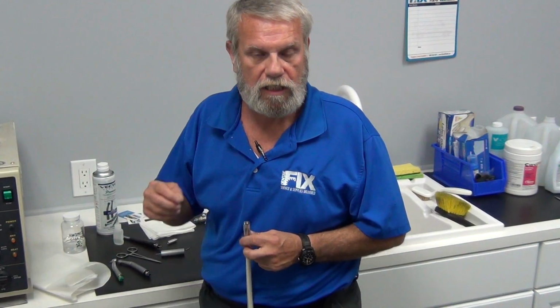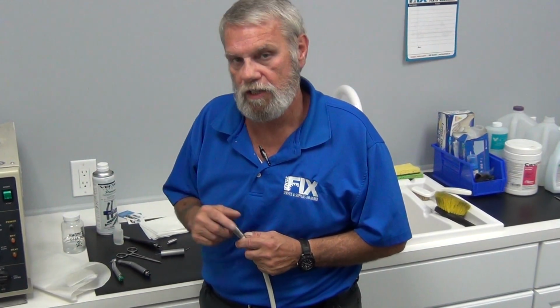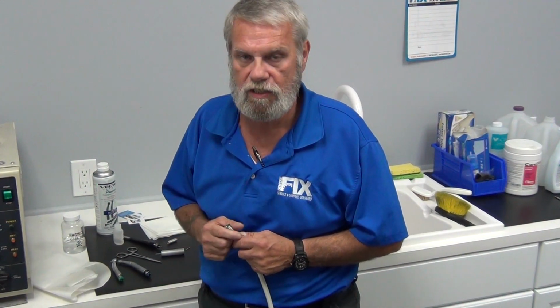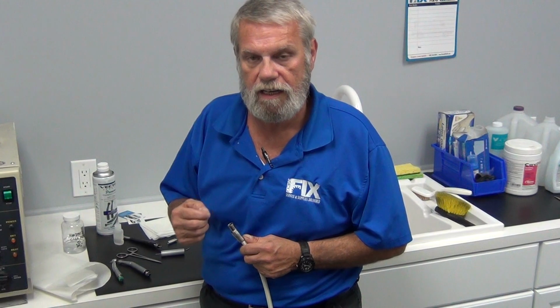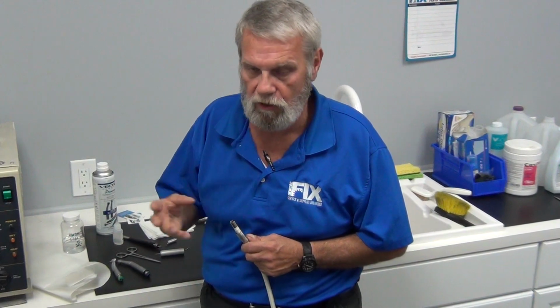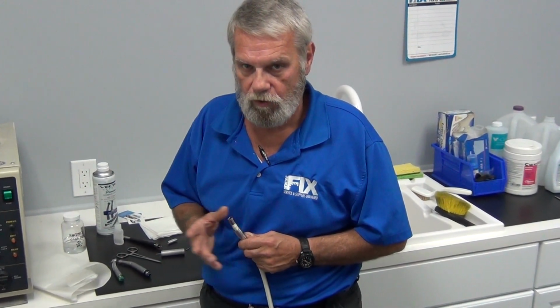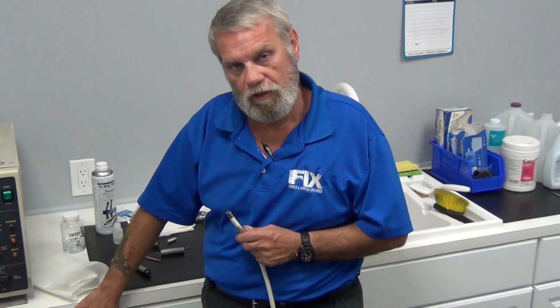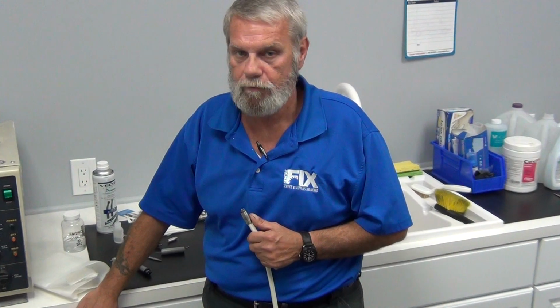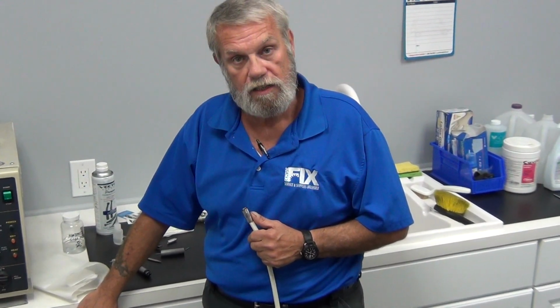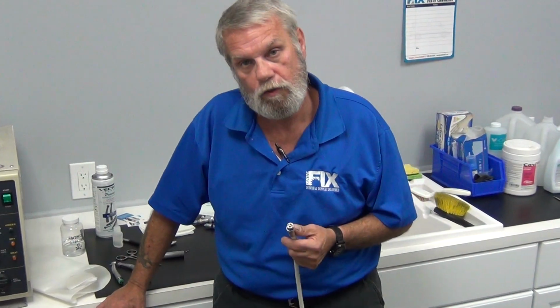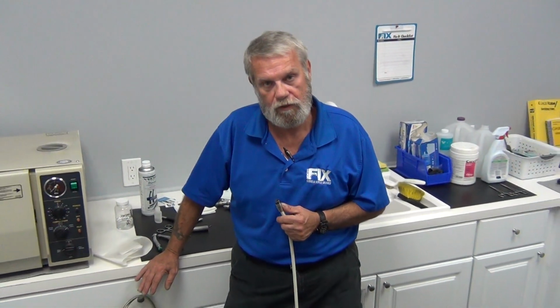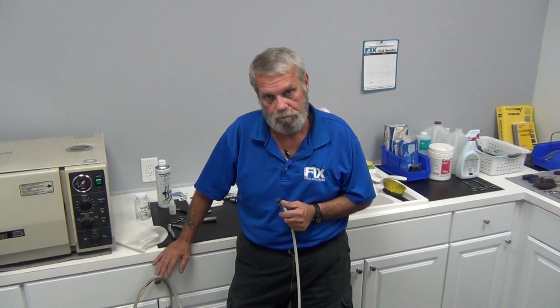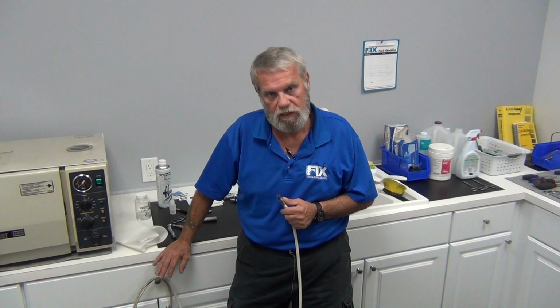If they're not purging these handpieces before they put them in, they're leaving a lot of oil in the head of the handpieces. Even though the oil is autoclavable, the oil will gum up after so many successive sterilizations. And it will get hard and get very viscous. It will really get gummy, and it will affect turbine life just as bad as if not lubricating it. So it's very important to purge, and we're going to go over the purge. Like I said, you have a sales opportunity here to sell a DCI purge unit. It's the same thing as a Quattro Care, or something as simple as just a foot control with a handpiece tubing. It's all a sales and labor opportunity for you, as well as a good public relations opportunity. And it will keep your warranties on handpieces down as well.